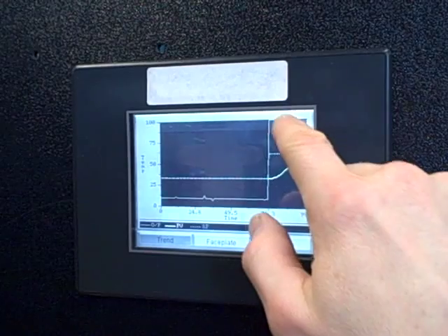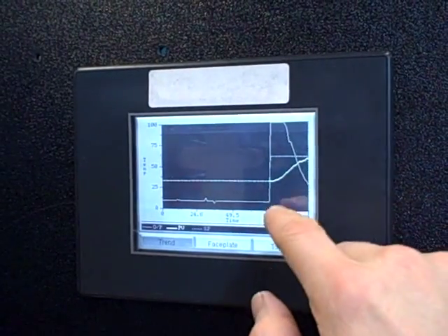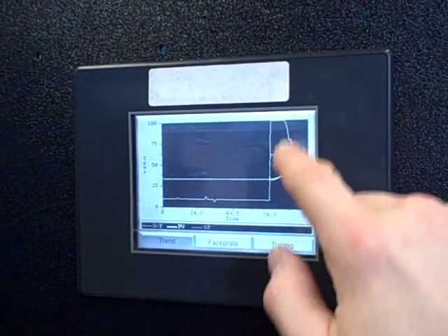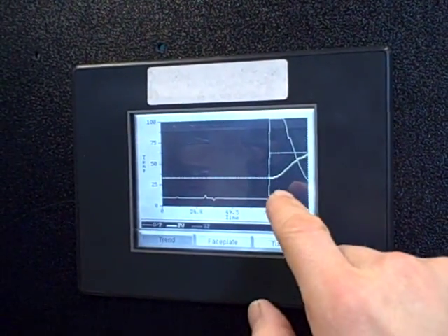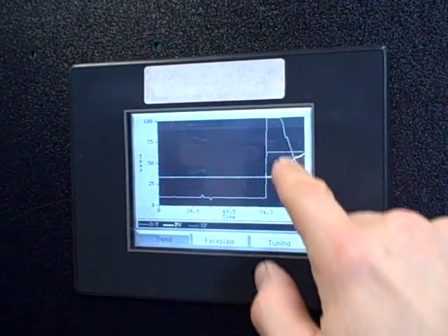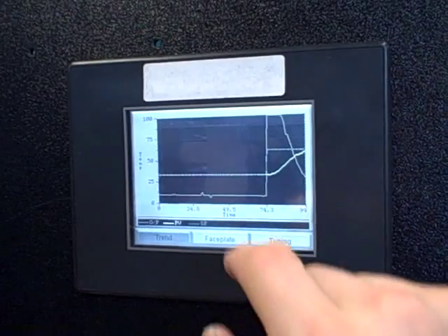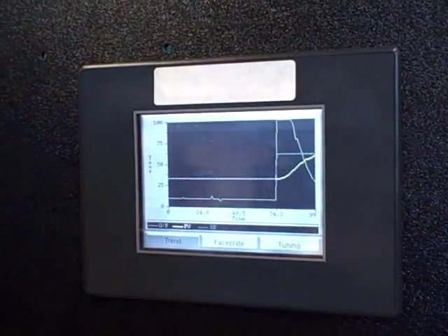The thinner white line is the output. It shot up immediately to put more heat to the oven, and now it's coming down as the process variable is approaching set point.